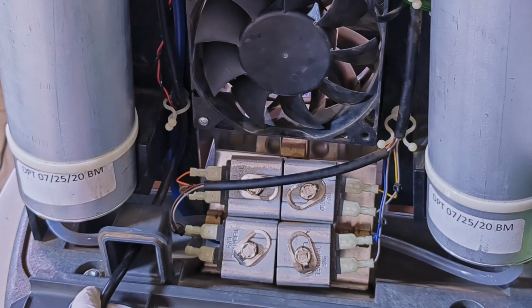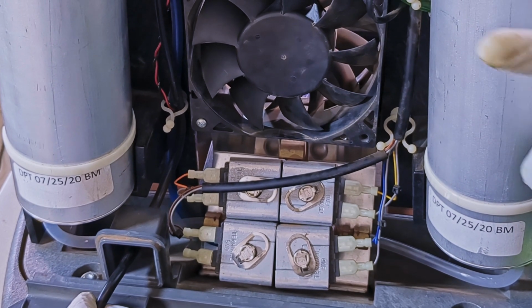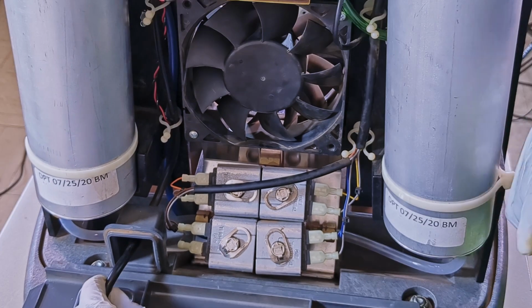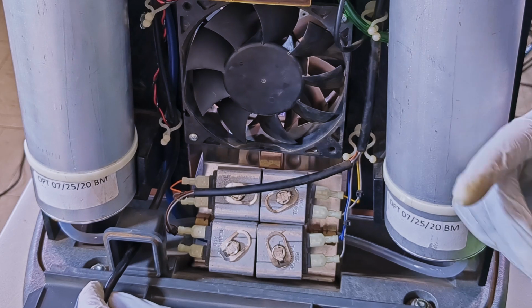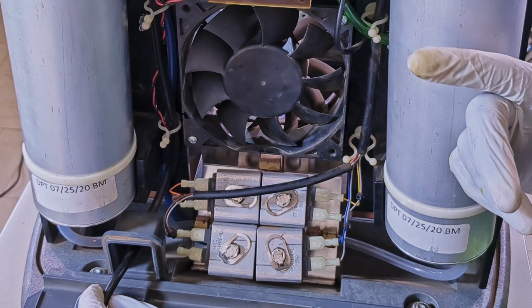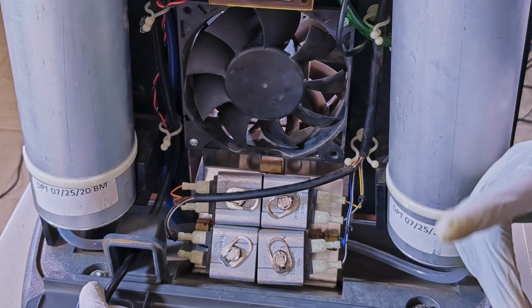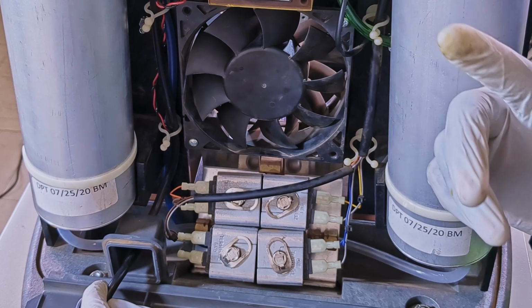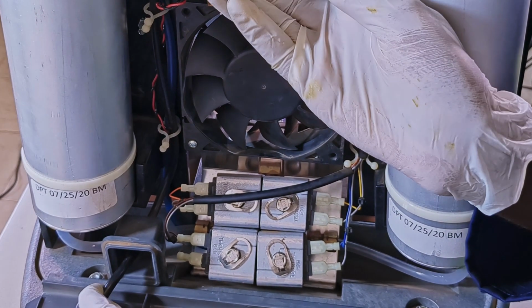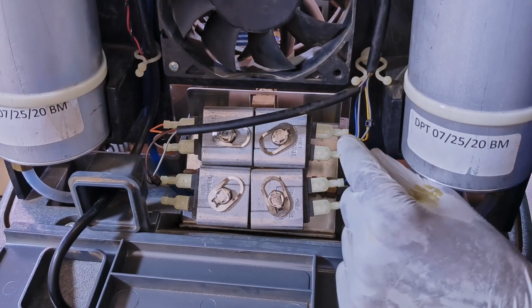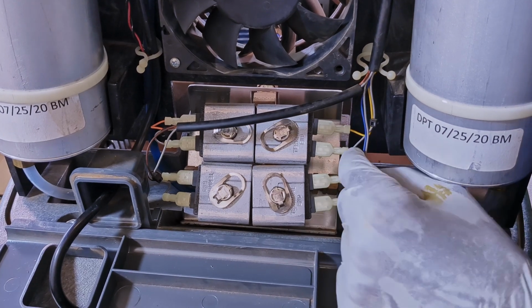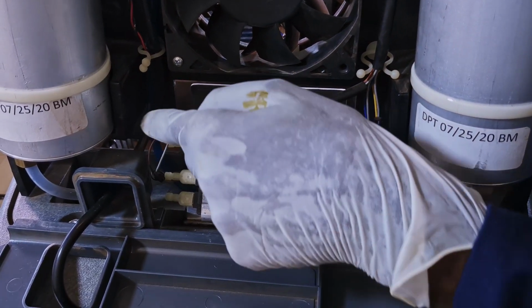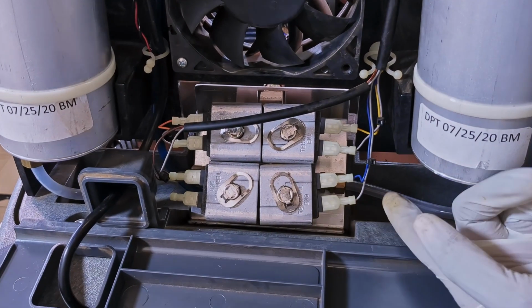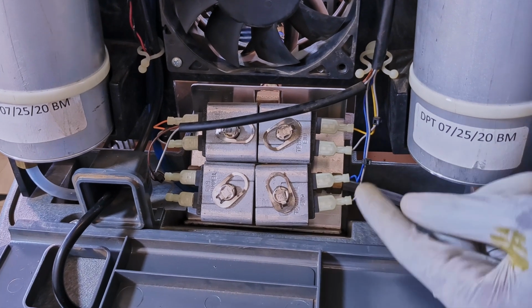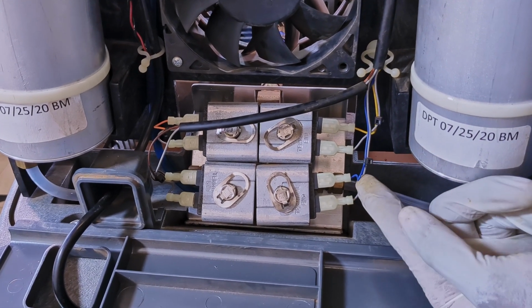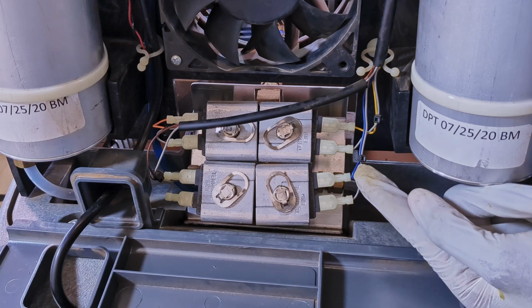Having looked at the parts of this oxygen concentrator, now let us look at its electrical system. As mentioned earlier, this unit operates on 230 volts AC. The 230 volts AC is supplied using this power cord. These cables here bring power to the 4 solenoid valves. Over here we have this one, which is the live cable, and this one, the blue one, the neutral cable.